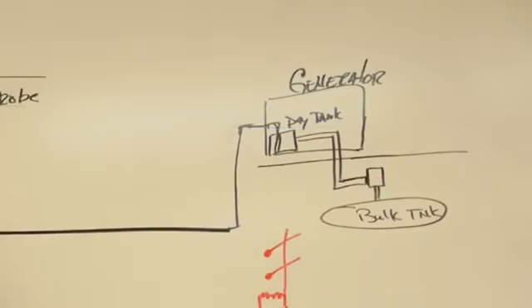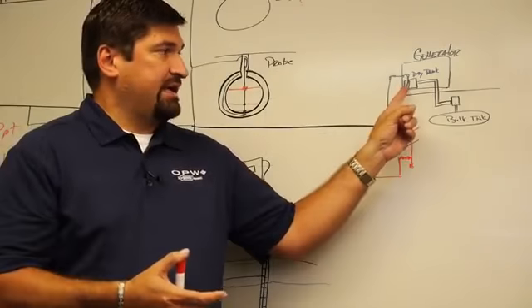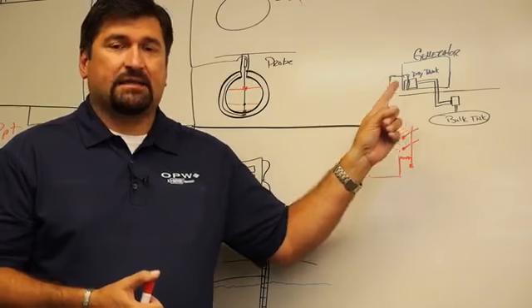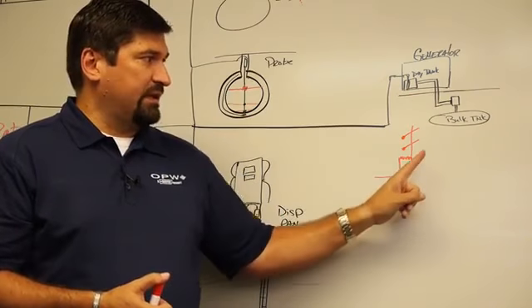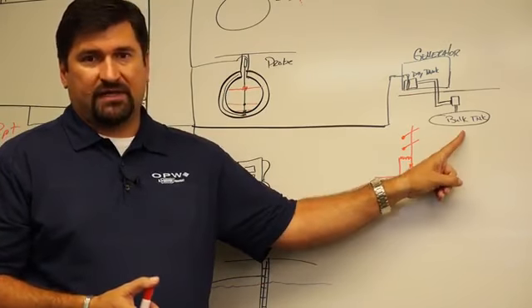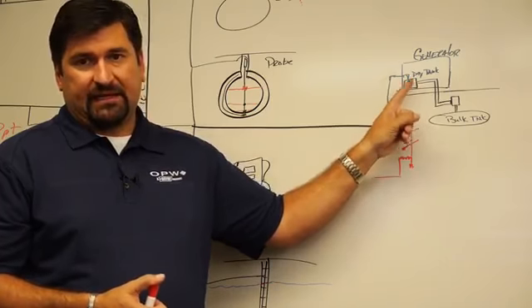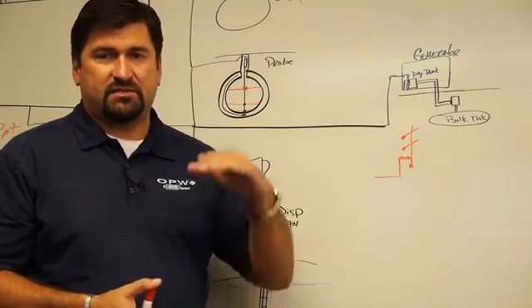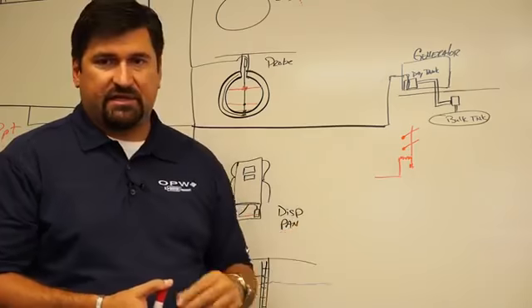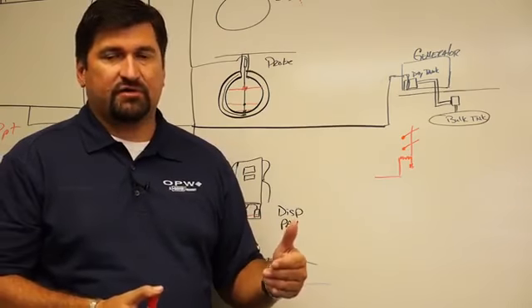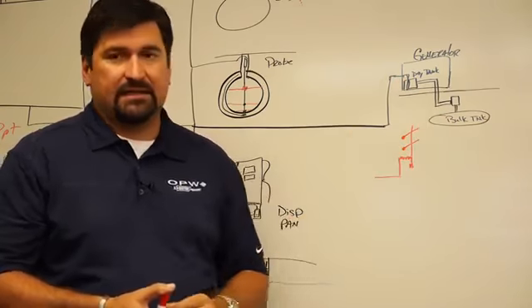If the generator kicks on and the day tank gets to a level where it needs to be replenished, the gauge would automatically read the day tank level. It can close the relay, turning on the transfer pump within the bulk tank, filling up your day tank, and then once the day tank reaches its full level, it would automatically de-energize the relay, turning off the transfer pump from the bulk tank to the day tank.